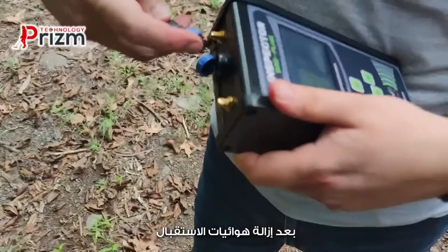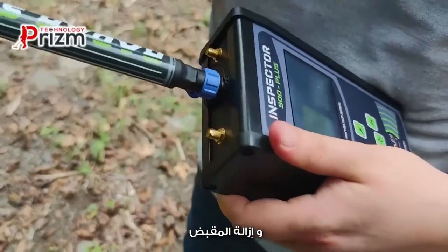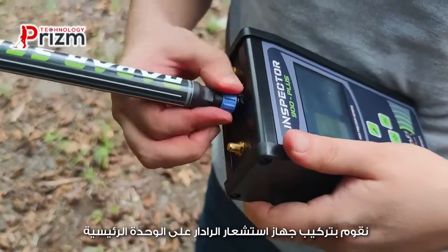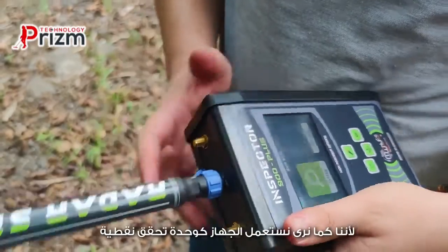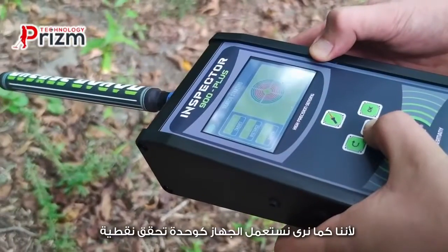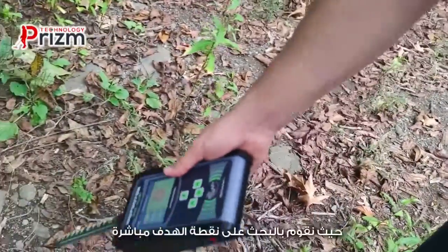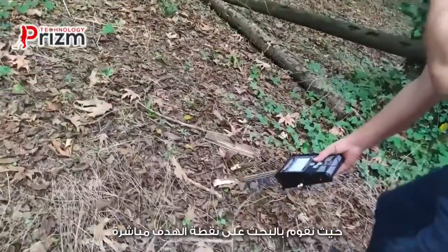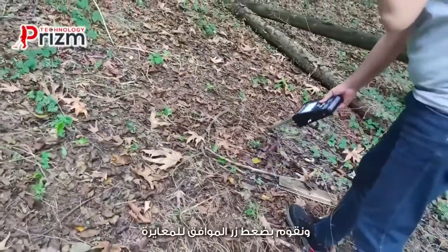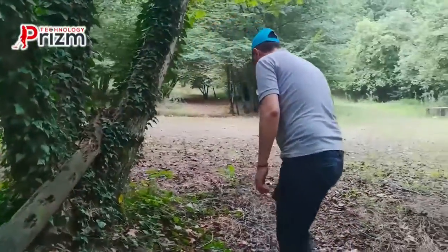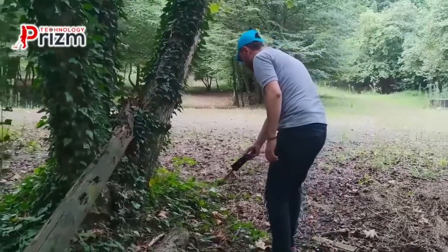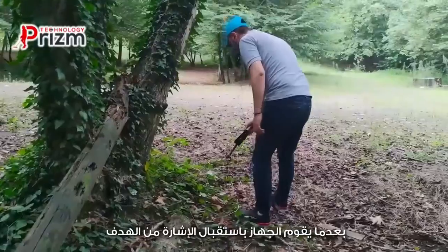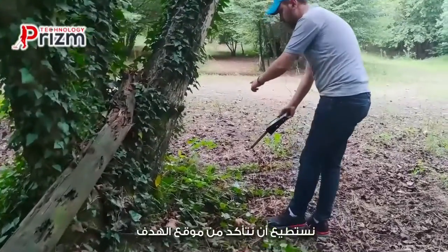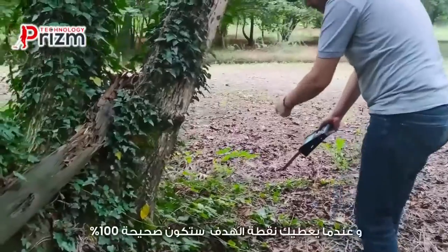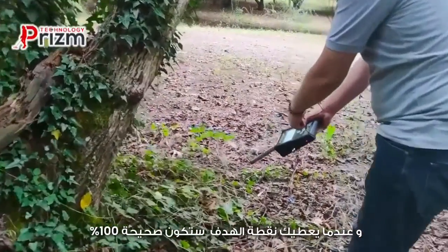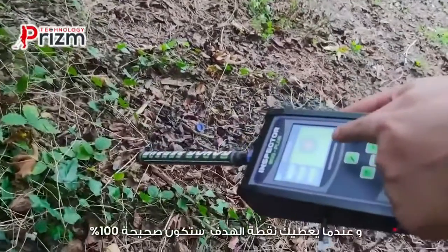After we remove the transceiver antennas, we remove the handle and we install the radar sensor in the main unit. We carry the device as we see and we use it as a point verification unit. We direct the device toward the target directly and we press the OK button for calibration. After the device receives the signal of the target, we could confirm the point of the target and dig in this point right in this place, and the target will be 100% in this point.